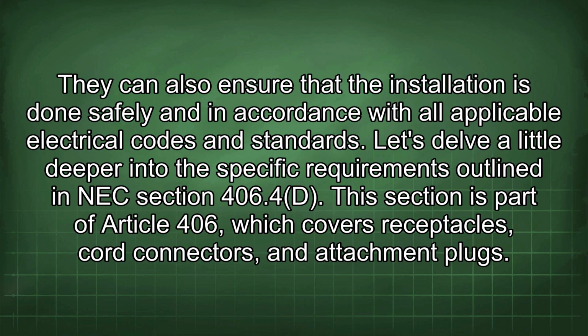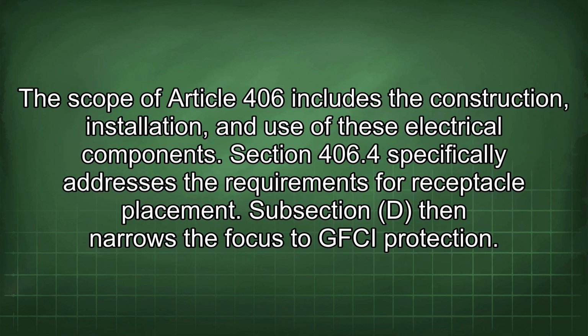Let's delve a little deeper into the specific requirements outlined in NEC Section 406.4(D). This section is part of Article 406, which covers receptacles, cord connectors, and attachment plugs. The scope of Article 406 includes the construction, installation, and use of these electrical components. Section 406.4 specifically addresses the requirements for receptacle placement. Subsection D then narrows the focus to GFCI protection.